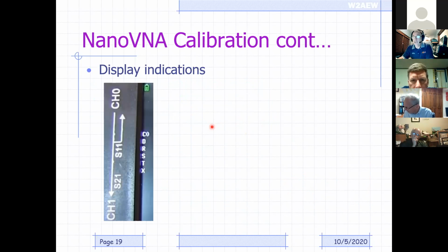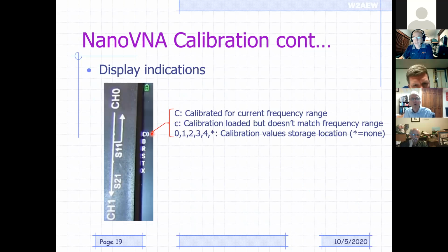So the display indications for calibration, I know I'm spending a lot of time on this, but this is the thing that most people get confused about. That's why I'm spending more time on calibration. The display indications for the calibration occur all the way on the left-hand side of the screen, and these letters all mean something. The first entry will show either capital C, meaning that I'm calibrated for the current frequency range. So whatever you did the calibration for, the measurement range matches that, and you're calibrated.